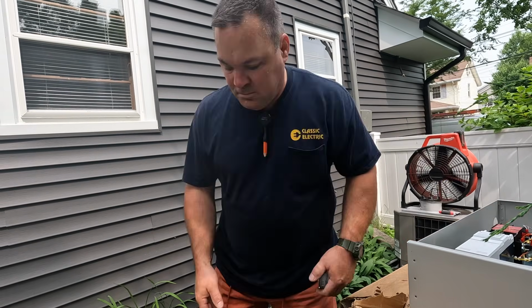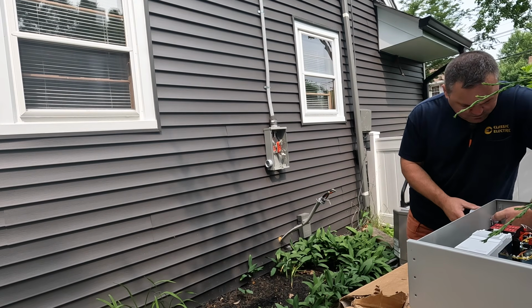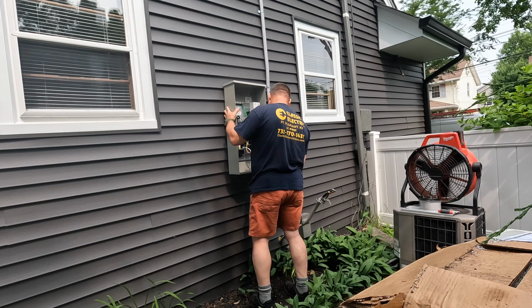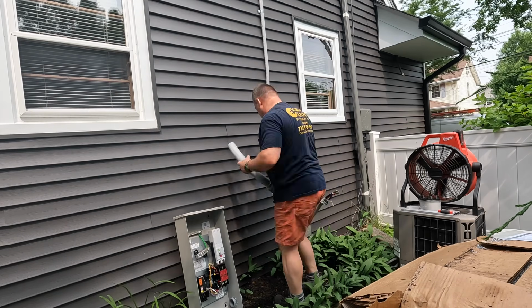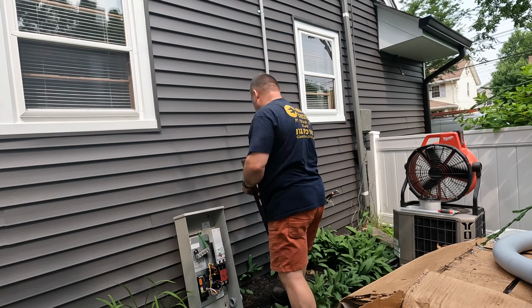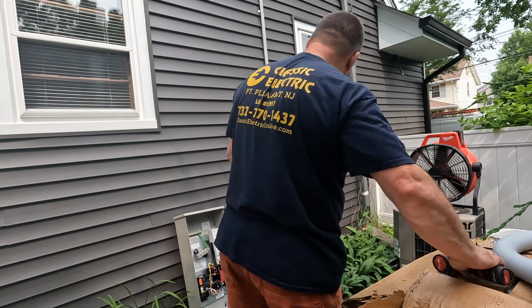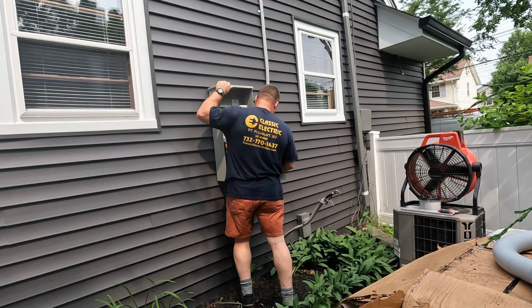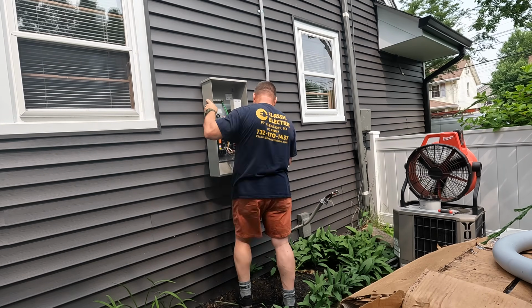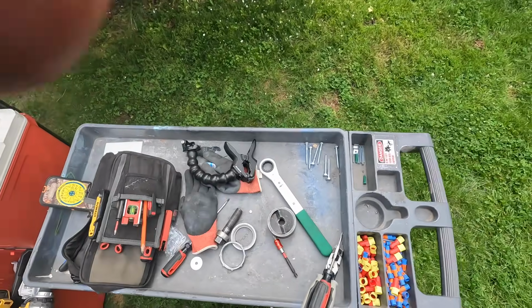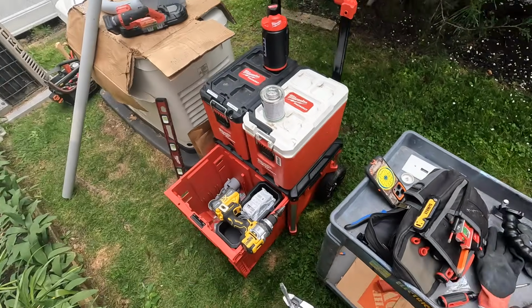You can see there I have it set up and realize it's the wrong one, so now I'm using this offset so my piece of conduit between the two will actually be even. Then I use the LB and a prefab 90-degree sweep, and marked approximately where I wanted my conduit to enter the transfer switch.